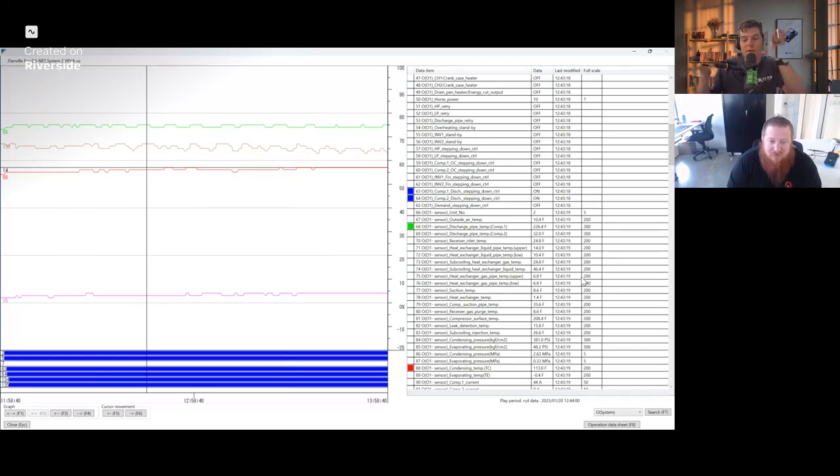When the temperature of my refrigerant goes from a cold substance to an even colder substance, right? I'm picking up heat in the wrong direction. You're like, wait a minute. Wait, what's your job? It's that Spider-Man meme where everybody's pointing at each other. Yeah. Right? I thought you were supposed to get the heat. No, you get the heat. What's going on here? So again, this system looks like it is really low on charge.